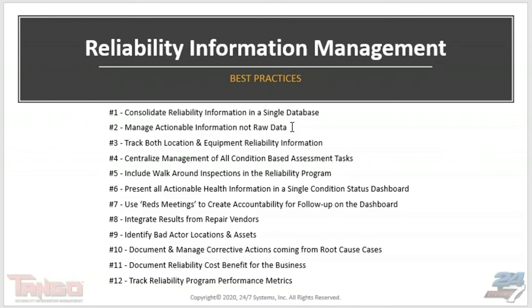Best practice number two: focus not on raw data like vibration spectra or infrared images — those are what technicians use to analyze — but on actionable information. I want to know what the technician has decided that information means, much like a doctor taking an EKG. I don't want the raw EKG handed to me — I want the analyzed results, the actionable information that comes out of that data, such as findings from vibration, infrared thermography, or repair shops.